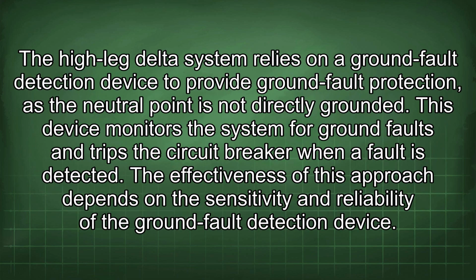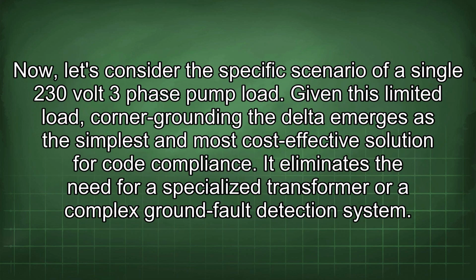The high leg delta system relies on a ground fault detection device to provide ground fault protection, as the neutral point is not directly grounded. This device monitors the system for ground faults and trips the circuit breaker when a fault is detected. The effectiveness of this approach depends on the sensitivity and reliability of the ground fault detection device. Now, let's consider the specific scenario of a single 230-volt three-phase pump load.